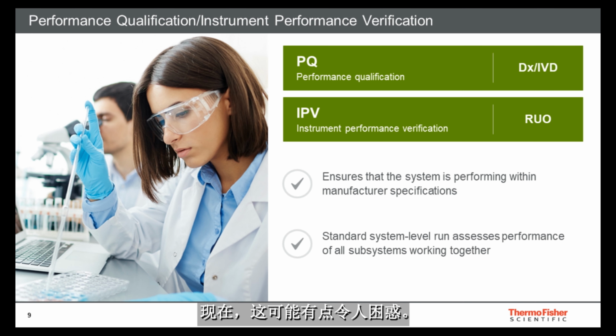Now, this might be a bit confusing. For most common understanding of a PQ or performance qualification establishes the limits and specifications for the entire workflow or process, including the equipment, instruments, and software. In the case of Thermo Fisher Scientific, the instrument hardware qualification PQ component is focused on the workflow of the instrument hardware as a product PQ, not as the larger workflow or process PQ that the instrument is being used in. Our hardware PQ establishes the utility of the instrument to a standard independently from its suitability for use in the total process workflow. Thus, the Thermo Fisher Scientific instrument hardware qualification becomes a supporting element in the larger process validation. Unfortunately, Thermo Fisher cannot perform the process validation for you.